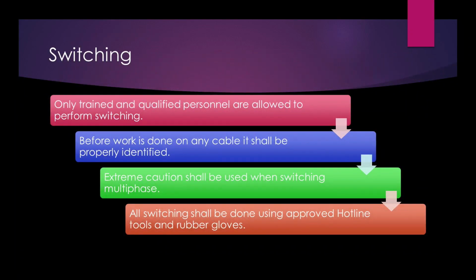When it comes to switching, once again, you've got to have trained personnel out there. Also make sure you identify the cable. It's a really good idea, because when you pop that elbow off and go, oh, what do you know, those lights went out, but they aren't supposed to. The lights over here were supposed to go out. It's always aggravating when you pull the wrong elbow off, especially for the people sitting in the house.